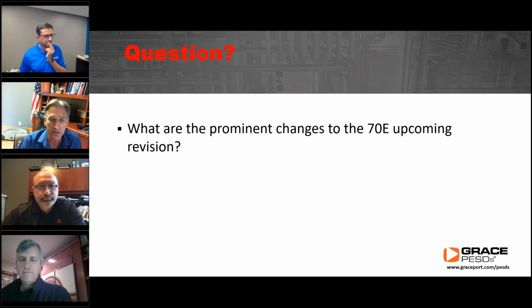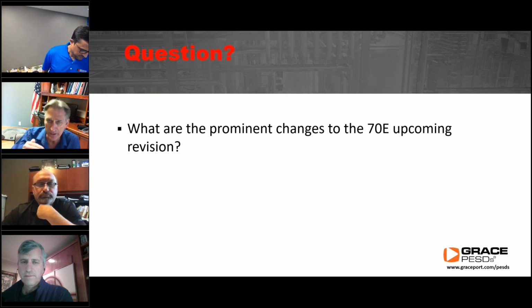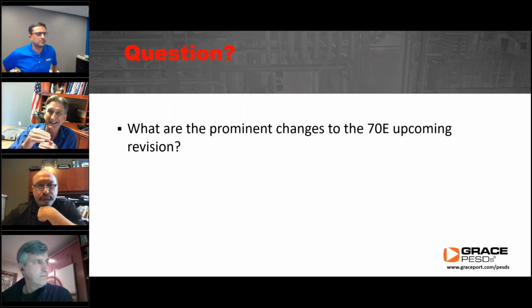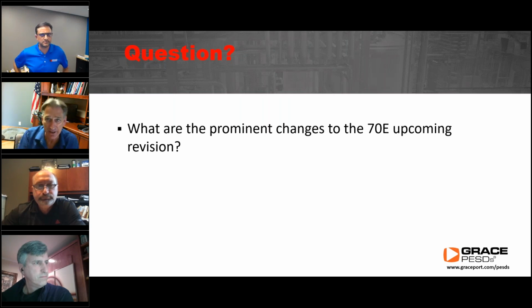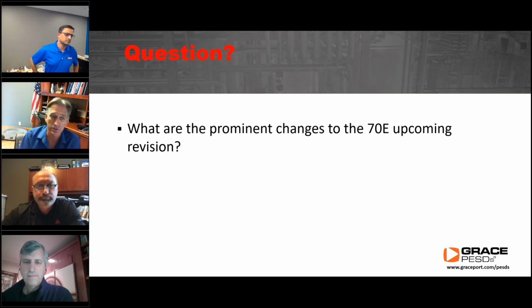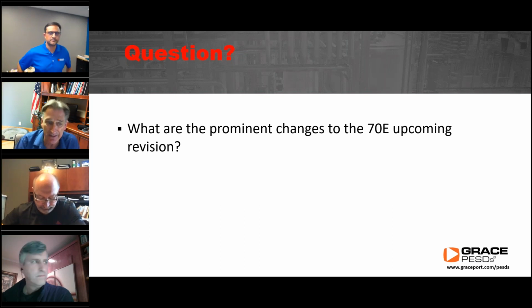There was a change in table 130.5. Remember, in 130.5 at the end of all the tasks it talks about normal operation of equipment. Well, that text that was in there sort of looked like a task, but it wasn't a task. So that text is taken out of table 130.5C, and a footnote is added saying equipment is considered to be in normal operating condition if all of the conditions in 110.4D are satisfied. It's saying the same thing, just taken out of that table.